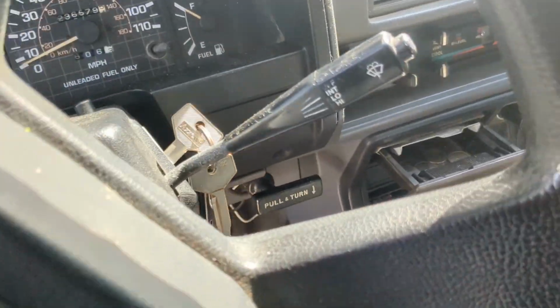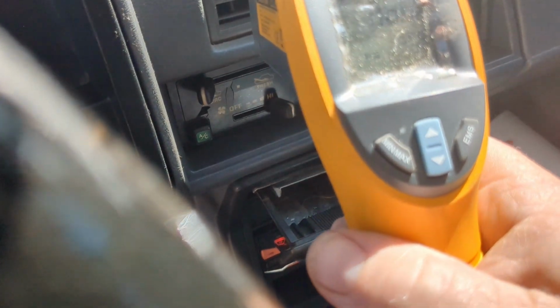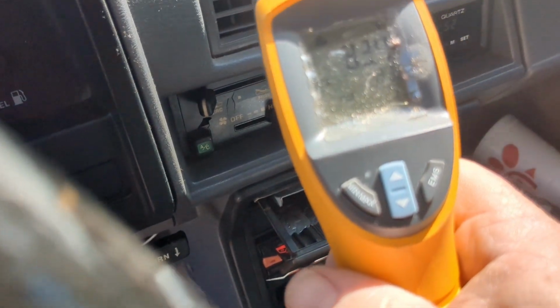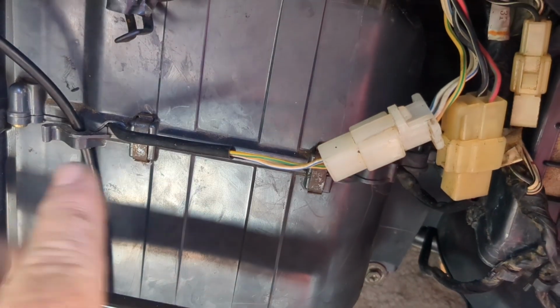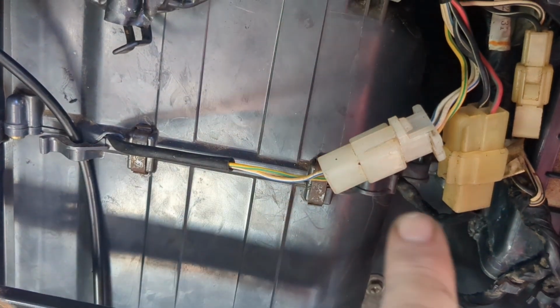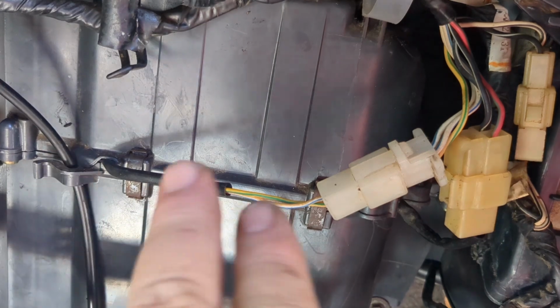Whenever your gauge pressures are correct and you've got not a very good temperature differential, you definitely have a heat load problem from somewhere. This box was put in, this is the evaporator box, and in place of this, when they were built without air conditioning or weren't added yet, there was just a piece of ductwork that went from this blower assembly across to the heater box.